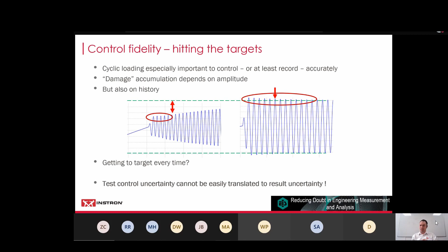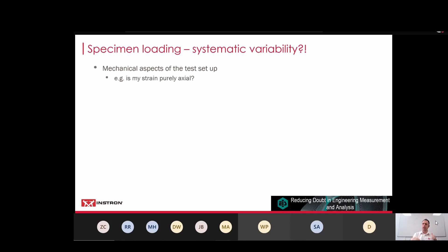So the other thing is specimen loading. Let's say we're getting the control, great, and I've put systematic variability with some sarcasm here, because is that almost nonsense? Well, maybe. So there are things that happen with the mechanical aspects of the test setup. Let's say we're doing an axial loaded test, and so it should be purely uniaxial. But is it? And this is perhaps something some of you have encountered, and it's the idea of gripping and getting accurate alignment. Now, if you clamp your test piece, and it's nicely aligned, everything's good. If you clamp it and one end has ended up offset or twisted, then you're now going to introduce some bending into your test piece.